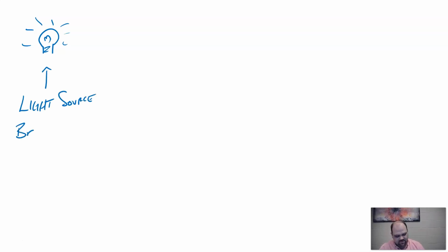We want a broad wavelength range, because in an ideal world, we'll only have one light source for every instrument that gives us as broad a range as possible. For some UV-Vis instruments, that's true. For some, they do have multiple light sources. We talk more about that in 411.